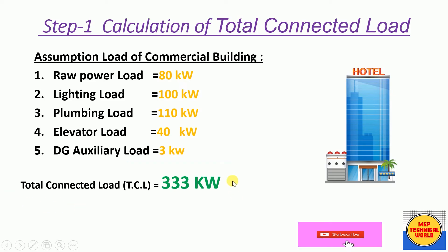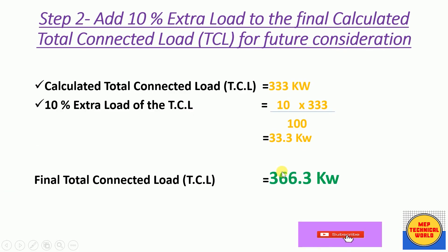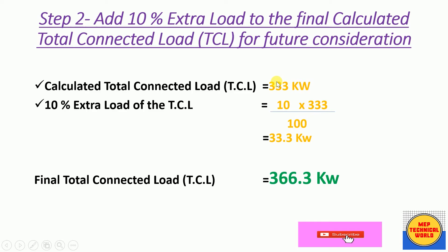In Step 2 we add 10% extra load to the total connected load for future consideration, because in the future the load may increase in various sectors. The total connected load calculated in the previous step was 333 kW. 10% of 333 kW = (10 × 333) / 100 = 33.3 kW. So the final total connected load (TCL) = 333 + 33.3 = 366.3 kW.